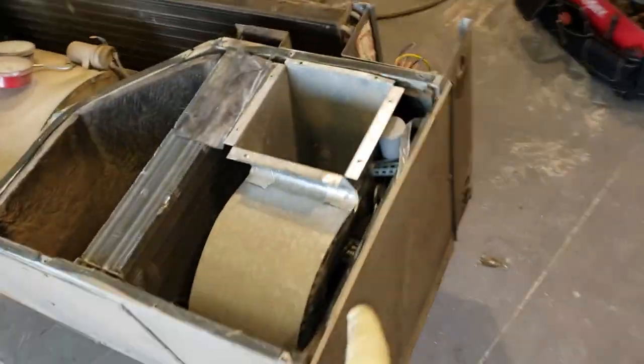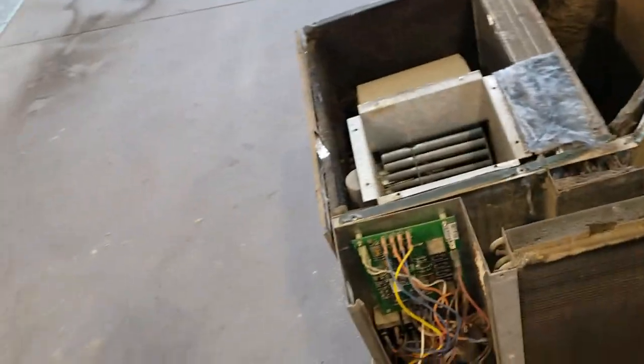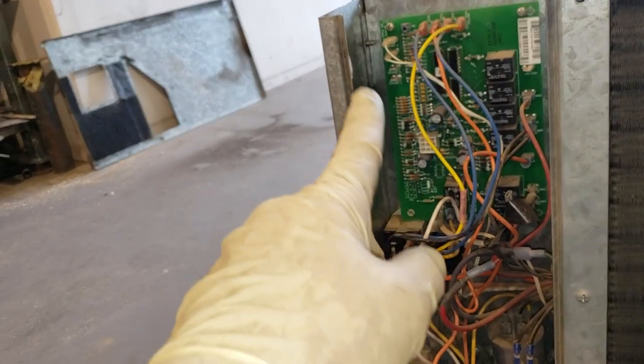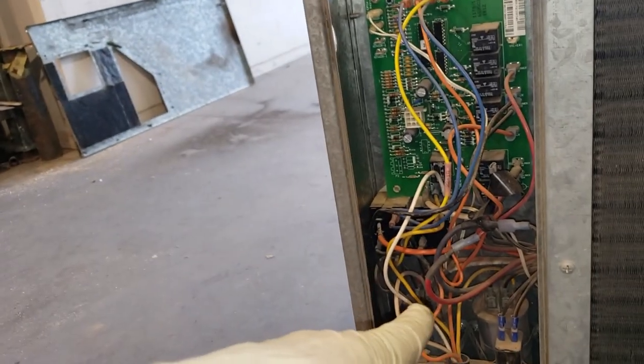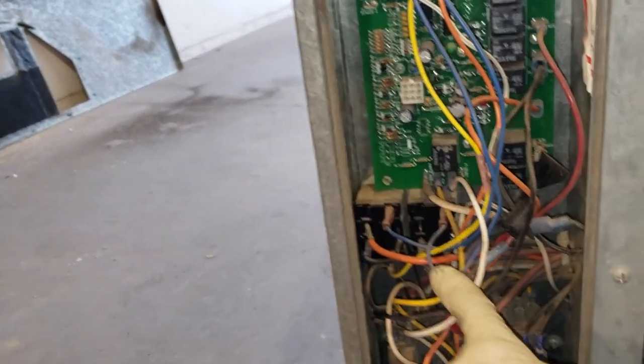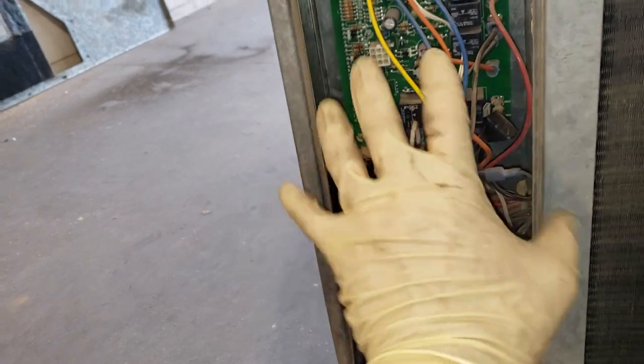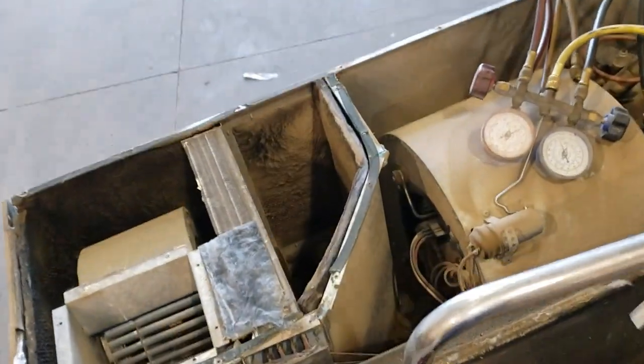All right, so this one is actually from a friend and a subscriber also. He didn't have any cooling going on his first stage compressor, so I did swap his first stage to a second stage. Well, his second stage to be a first stage, so at least he had some cooling. But it was pretty evident that there was some sort of leak here. So I got it pulled out of his basement.